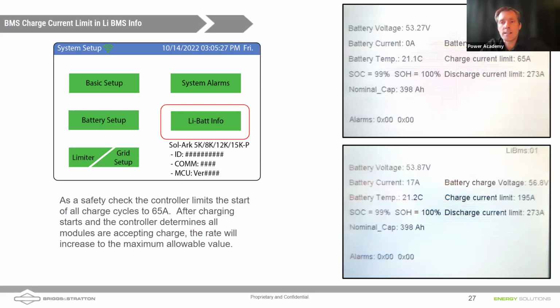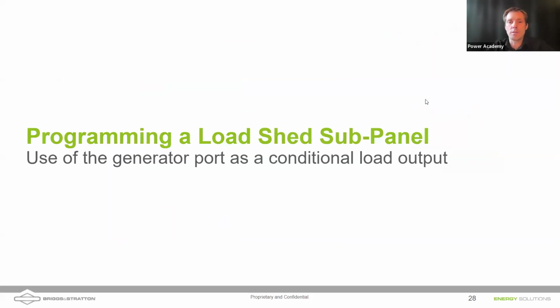So if I had a stack of 6 batteries, it's going to make sure those batteries are accepting charge before increasing that charge limit. For a stack of 3 batteries, after the charging has initiated, you'll see that charge current limit automatically move up to let you know all 3 batteries are accepting charge. So don't be alarmed if you see a charge current limit that doesn't match what you think it should be. As soon as a charge cycle initiates, the battery will automatically adjust that charge rate.